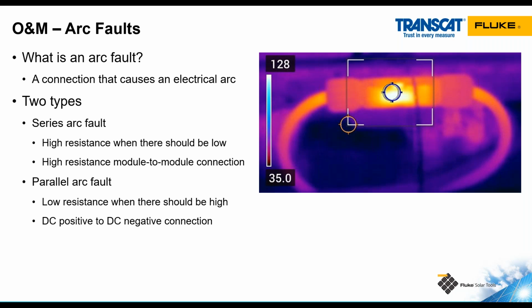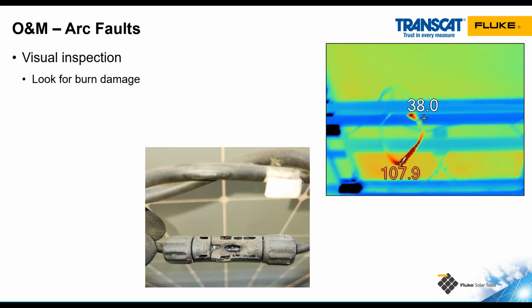An example would be the DC positive and negative. Maybe they rubbed together and the insulation wore away, and now that positive and negative is arcing and making a connection. I can do a visual inspection to find arc faults, where I'm looking for burn damage. I can also use a thermal camera to identify components that are hotter than other similar components under similar conditions, like module interconnections.